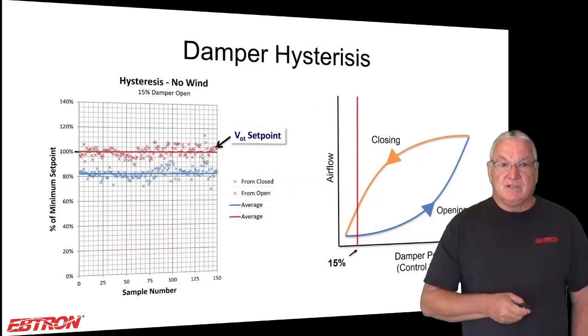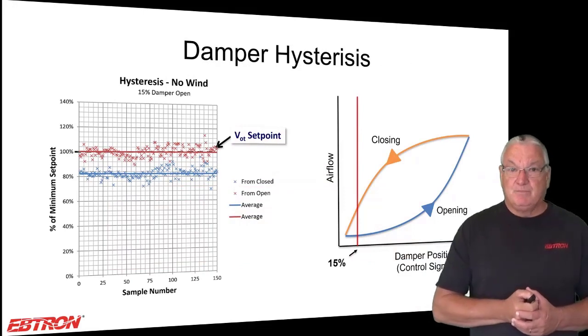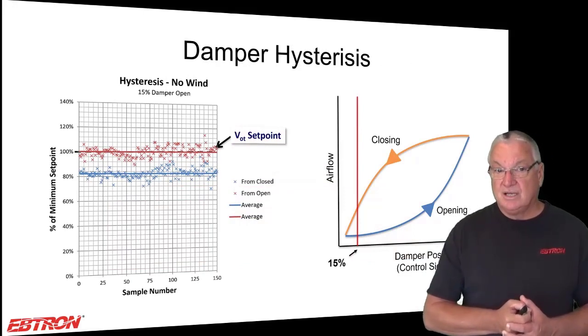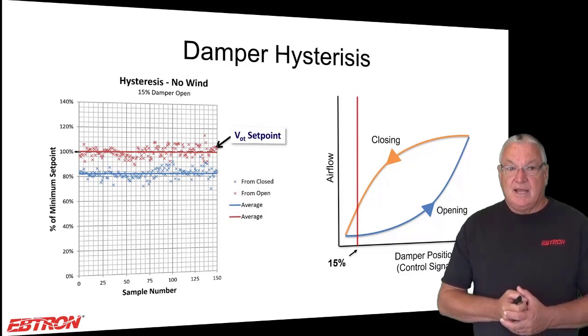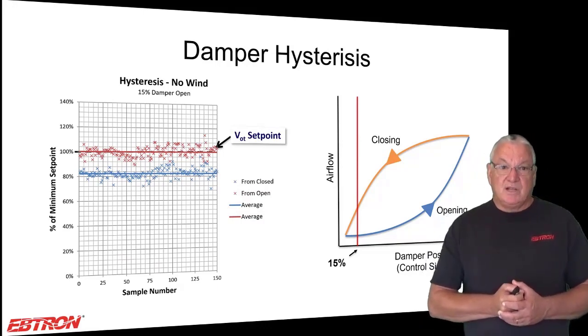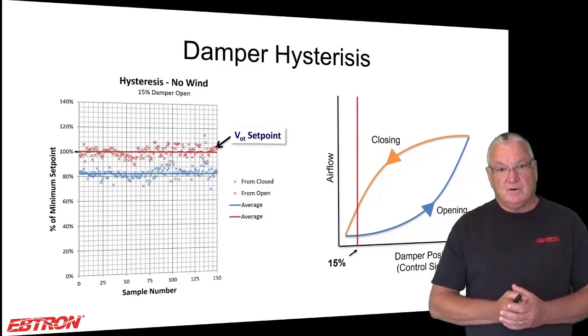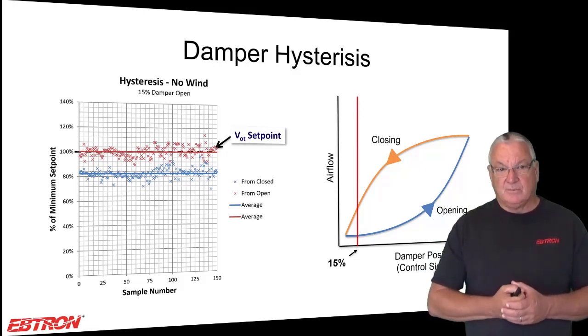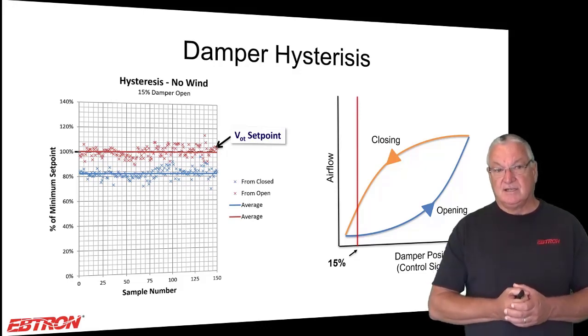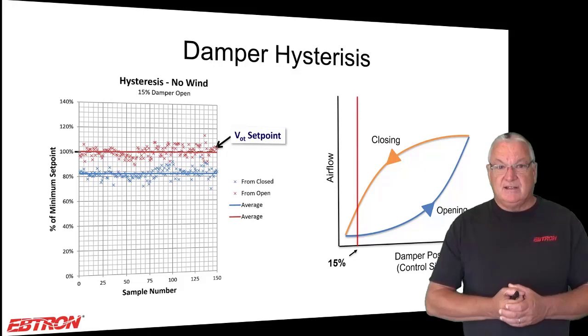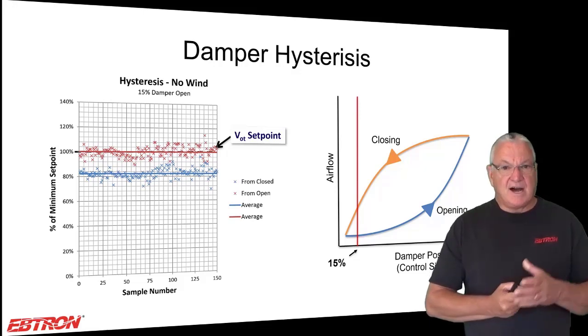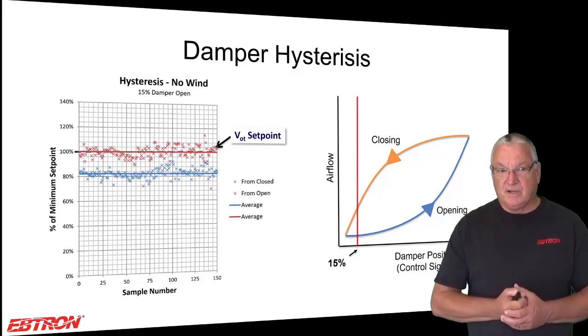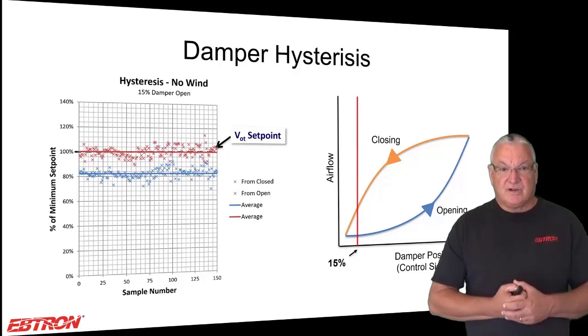The only thing I'm going to really show you here is from our building with a very high quality damper. All we did is we went from night setback mode to 15% open, or we went from 100% economizer to 15% open, and we measured the outside airflow rate with everything else being constant. What you see there is the red data set was from economizer to 15% open, and the blue data set is from night setback to 15% open.